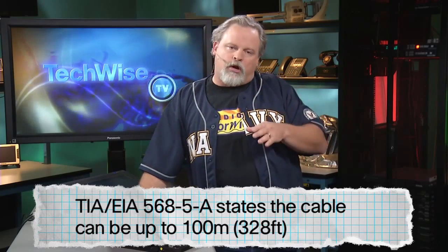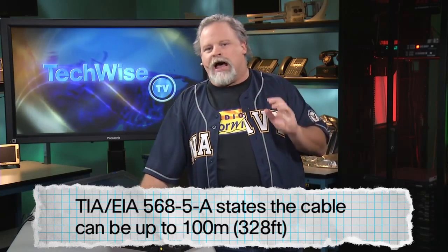Cat6, being 200 megahertz, is going to give you a lot better resolution. You're going to have a much higher signal to noise ratio, so you don't have a lot of those crosstalk issues at the far end when you start running at higher speeds, 10 gigabit, 40 gigabit. Well, 40 gigabit's not rated on copper yet, but you never know. The 10 gigabit stuff certainly is, and I definitely would recommend going Cat6 on that.